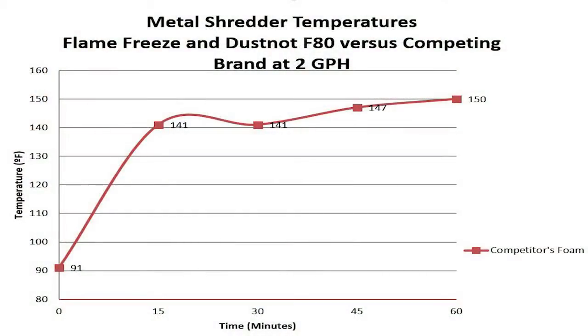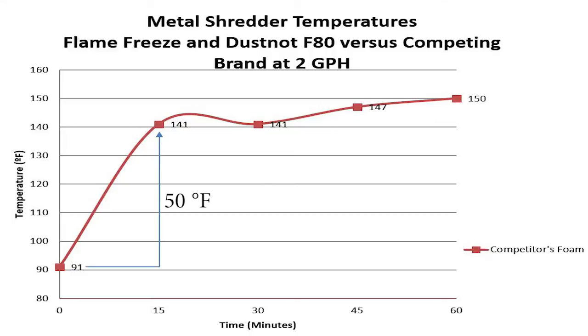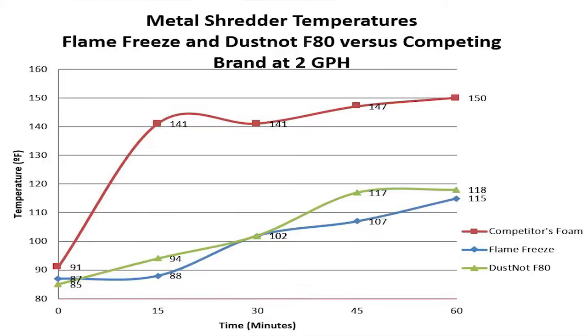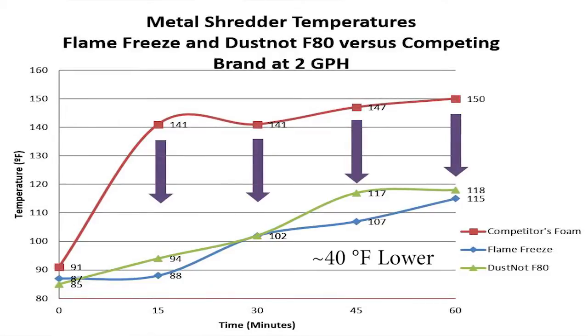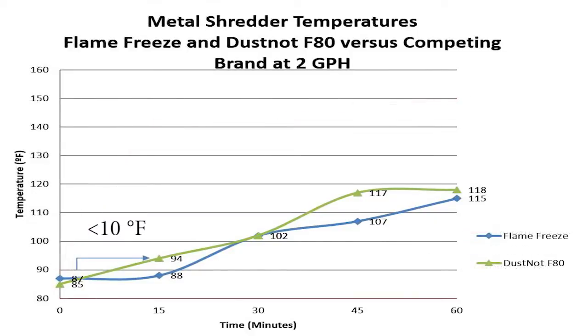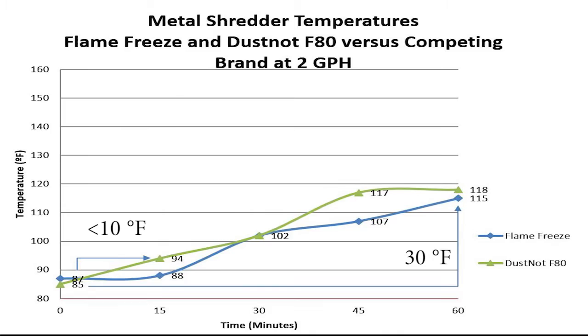The study was conducted in order to demonstrate the temperature-reducing properties of the Flame Freeze technology. As the graph clearly demonstrates, when using the competitor's foam, the temperature of the shredder box increased 50 degrees Fahrenheit in only 15 minutes, and nearly 60 degrees Fahrenheit within an hour. At the same dilution rates and feed rates as the competitor's foam, the Momar products were able to maintain much lower operating temperatures. With both Flame Freeze and Dustnot F80, the temperature increased less than 10 degrees Fahrenheit in the first 15 minutes, and only rose 30 degrees Fahrenheit during one hour.